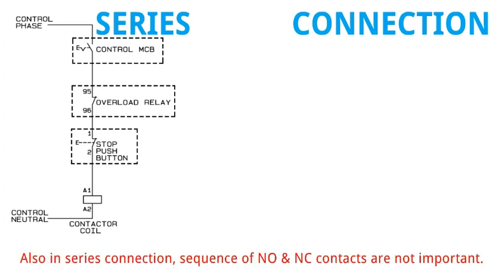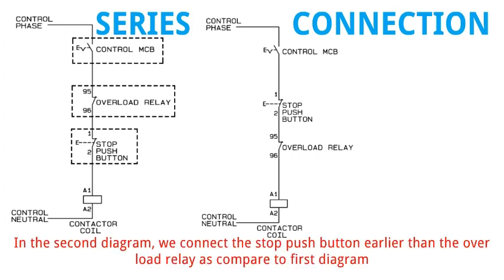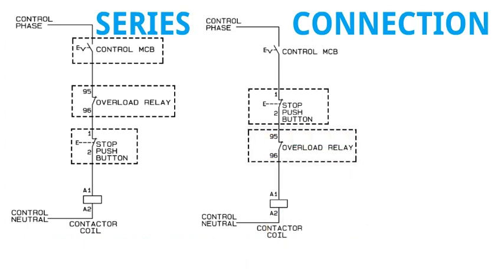Also in series connection, sequence of NO and NC contacts are not important. Look at another diagram. In the second diagram, we connect the stop push button earlier than the overload relay as compared to first diagram. But the working of both drawings are same.